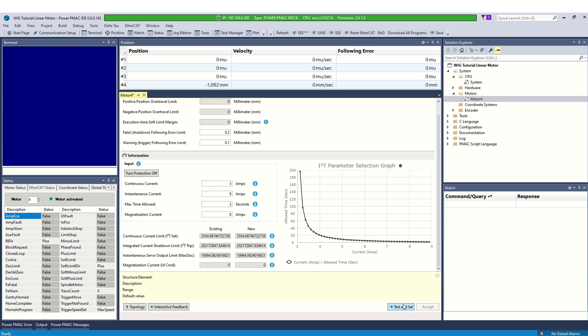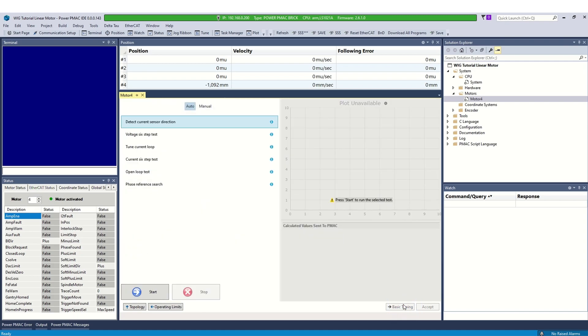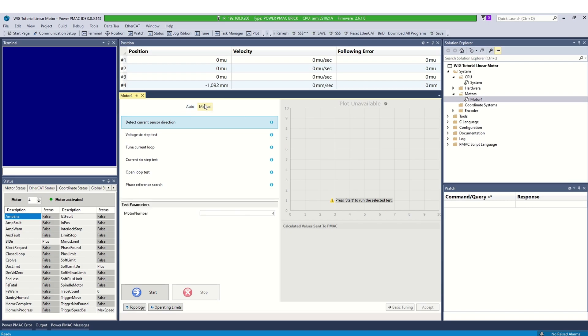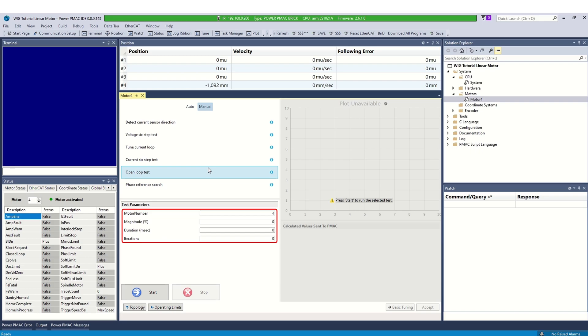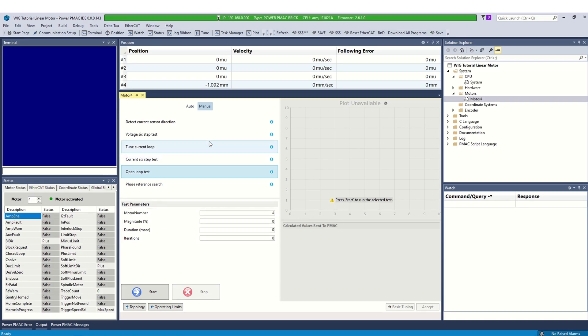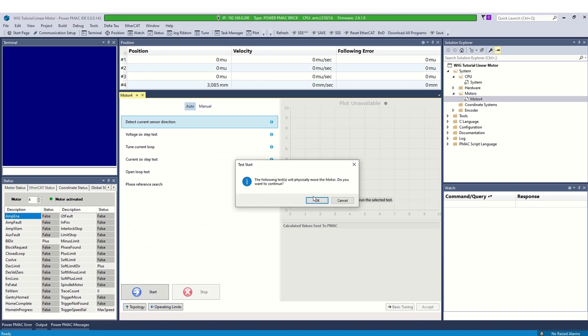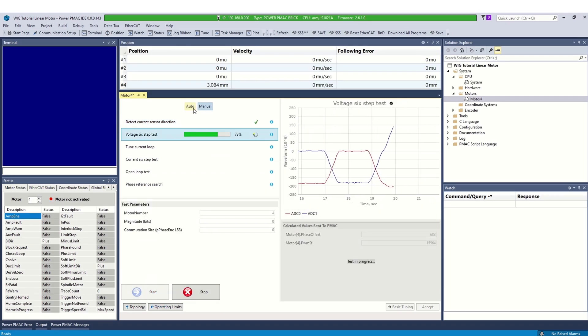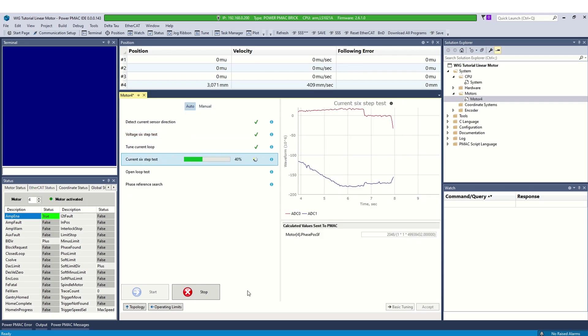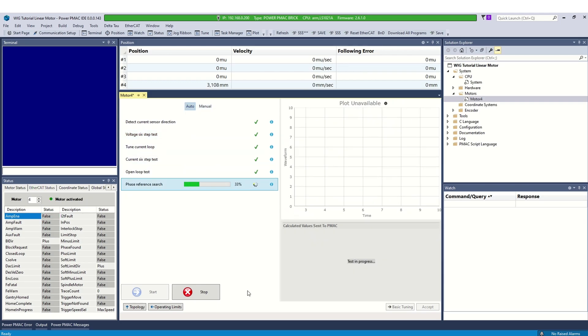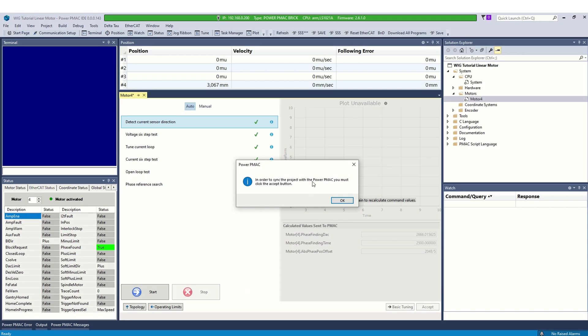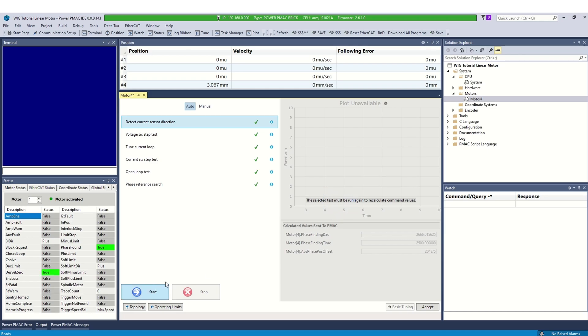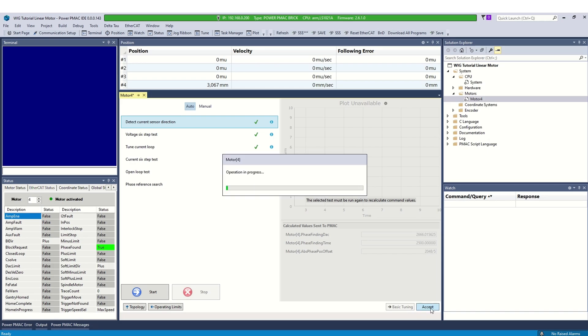At this point, all the motor parameters are configured. The test and set block performs a series of tests to evaluate motor parameters. In auto mode, predefined tests are performed to configure the motor. In manual mode, user can specify values of parameters for each test and execute them in sequence. Simply select start in the auto mode. The software will run this test in sequence. Once complete, a message will prompt asking you to save this configuration. If the test fails, that means one of the parameters in the setup is incorrect and should be addressed by looking at PowerPMac message window.